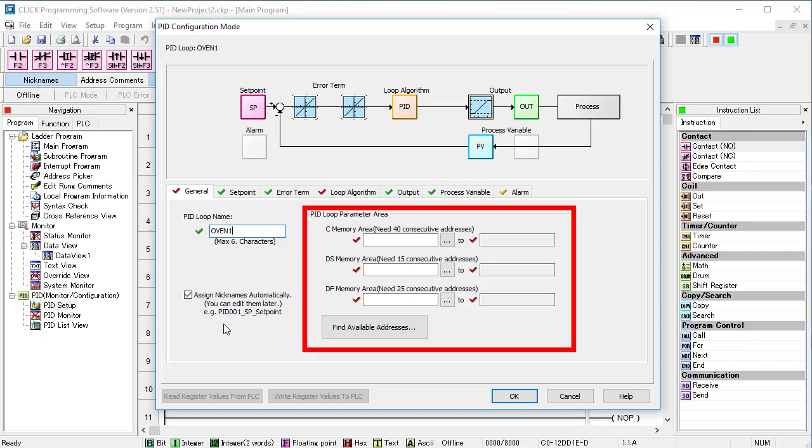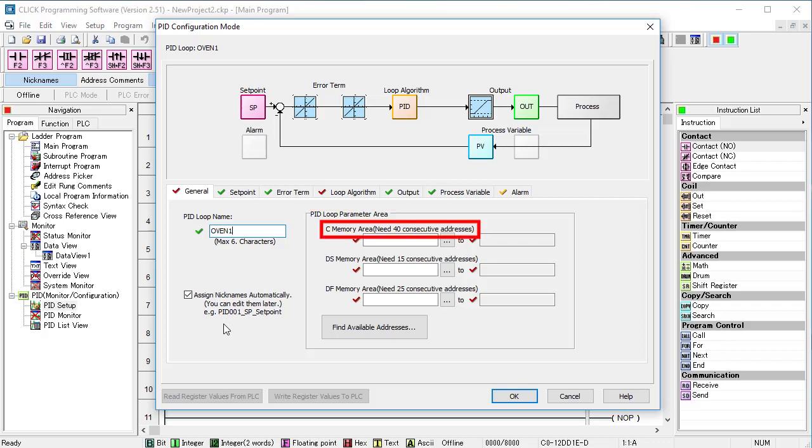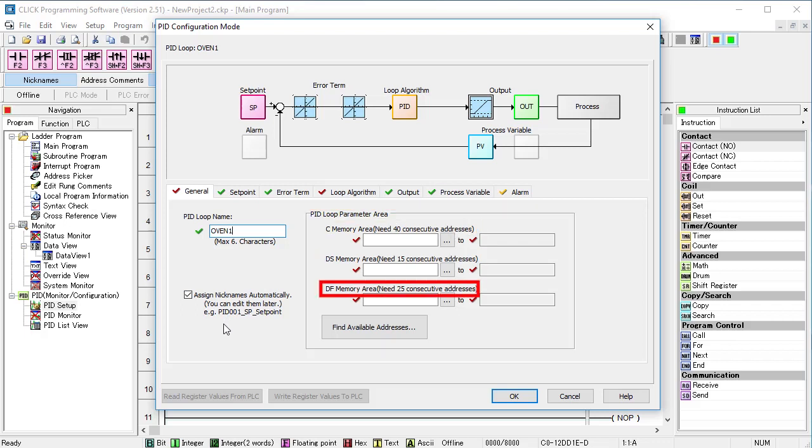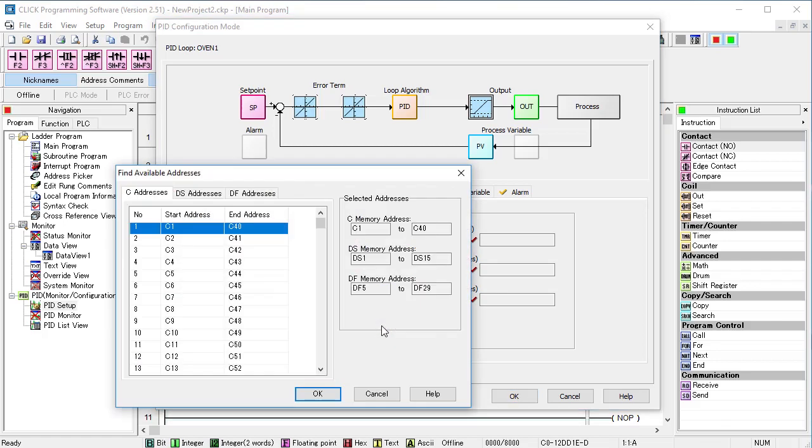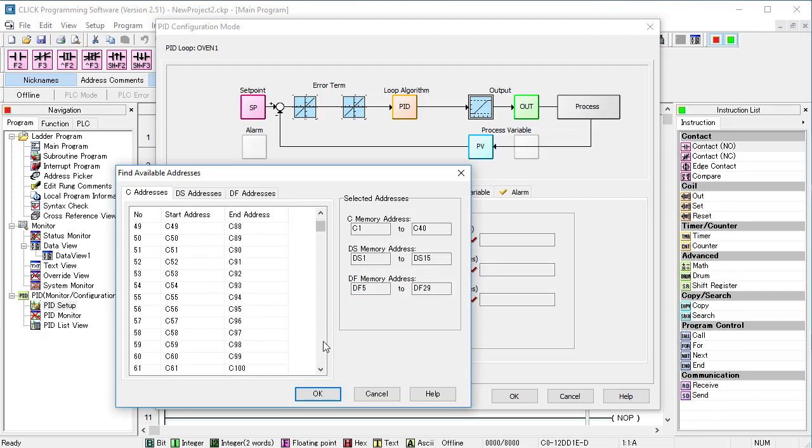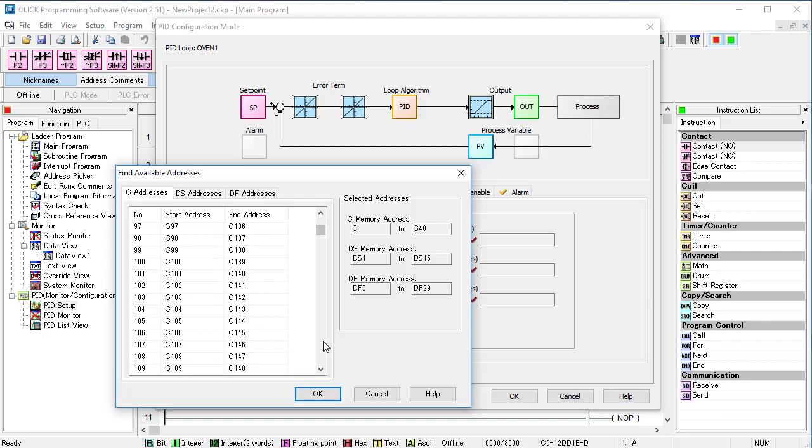Next we need to allocate memory. Looks like we need 40 C bits, 15 integers and 25 floats. We could enter the starting address ourselves and hope there's no conflicts, but it's so much easier to let the software help you by clicking on Find Available Addresses. It scans your code and finds all of the available blocks of contiguous unused memory locations and lists them here. We don't have any code, so of course everything is available. But if you try to add PID to an existing project, this is a real time saver.